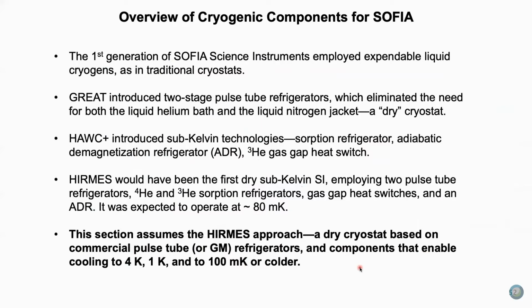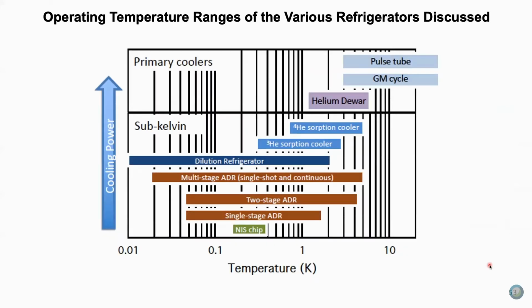Now, this section assumes that the HIRMES approach is a good approach - a dry cryostat based on commercial pulse tube or Gifford-McMahon refrigerators, and components that enable cooling to 4 Kelvin, 1 Kelvin, or down to 100 millikelvin or colder.